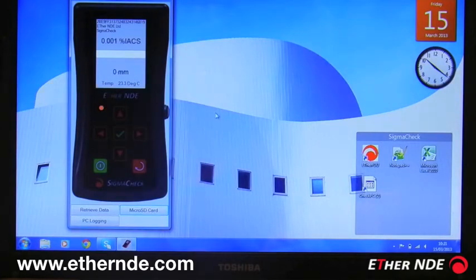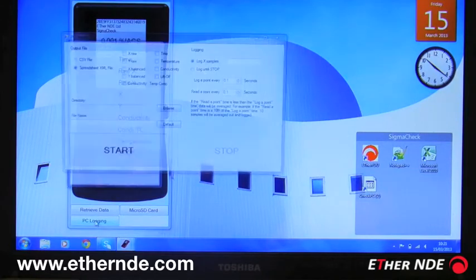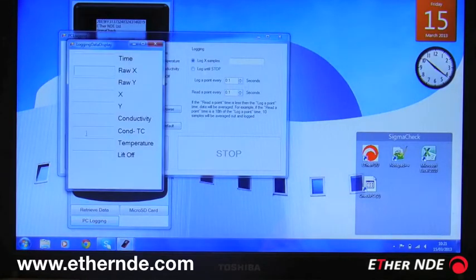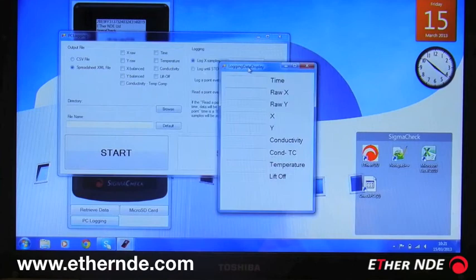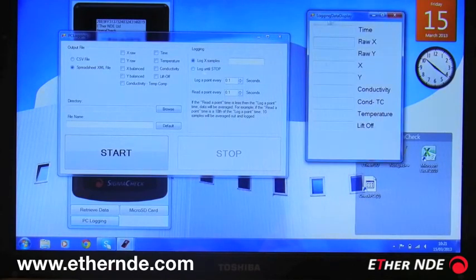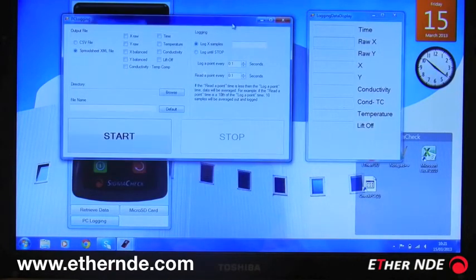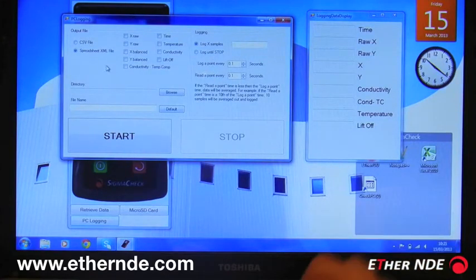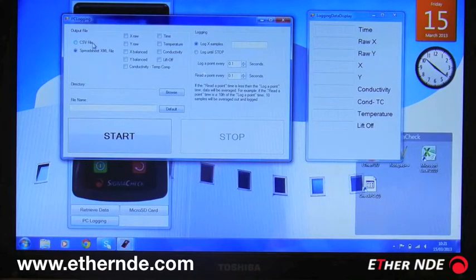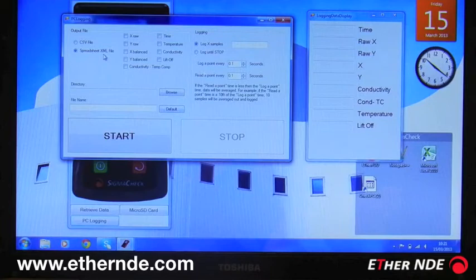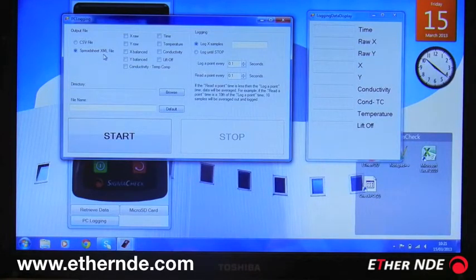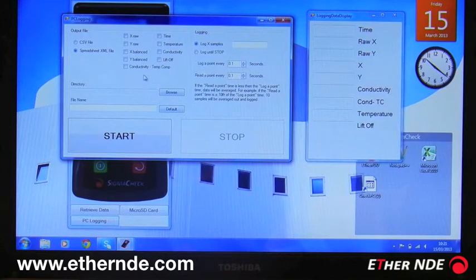The final button is PC logging. This gives us the ability to log data seen by the SigmaCheck over a long period of time. Roughly explaining the buttons on here, it can be outputted to a CSV file stored on the laptop or an XML file. The XML file can then be read by any spreadsheet package.